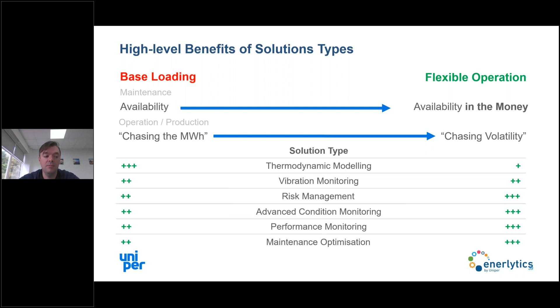And then your maintenance optimization becomes more valuable because in a base loading regime, every 4 years you're going to do your major statutory outage. But in a flexible operating regime, you could end up doing a major one every 3 years because of lots of starts and stops, or every 6 because your operation is different.